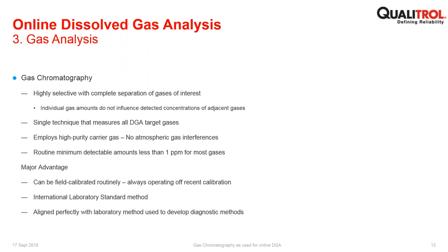The major advantage of gas chromatography for gas analysis is that it can be routinely field calibrated. In the case of online DGA systems, that is once or twice per week. The real benefit that provides is that you're always operating off a recent calibration. For systems that cannot be calibrated in the field, you are operating off a calibration that may be a number of years old. And where it is necessary to make some critical decision about your transformer, a calibration that is a number of years old may not provide you with the confidence to do so.